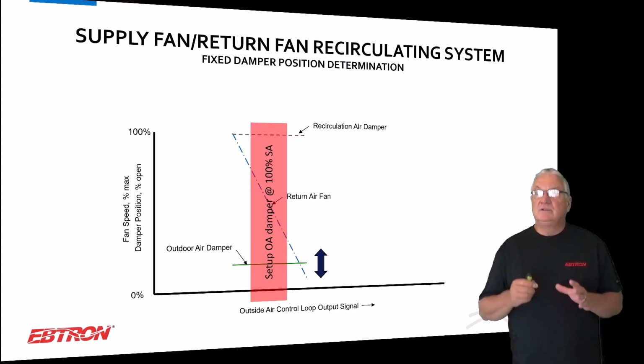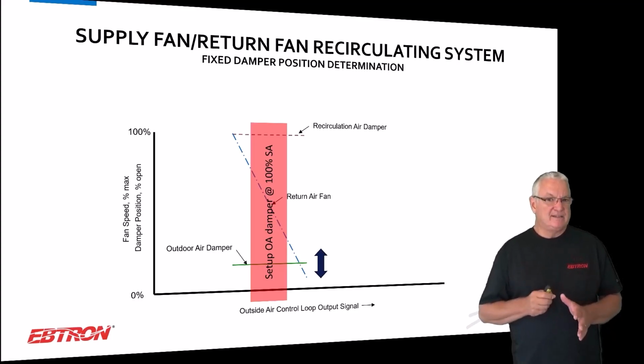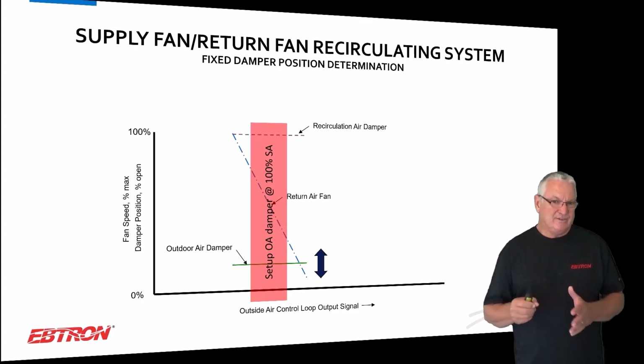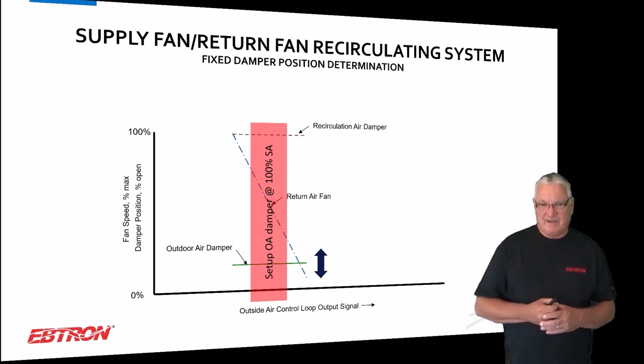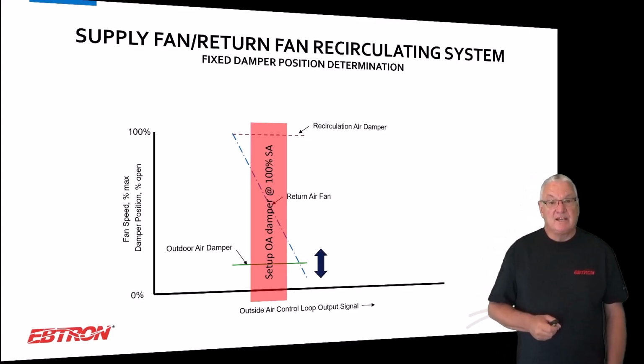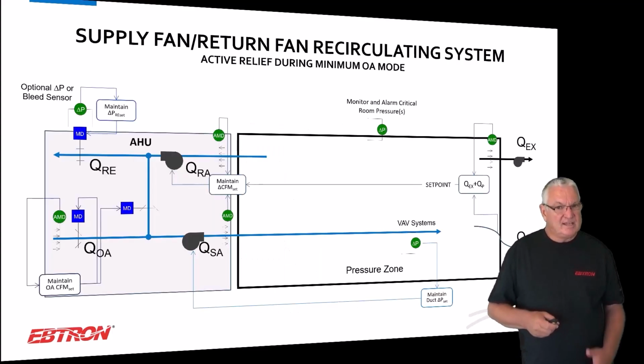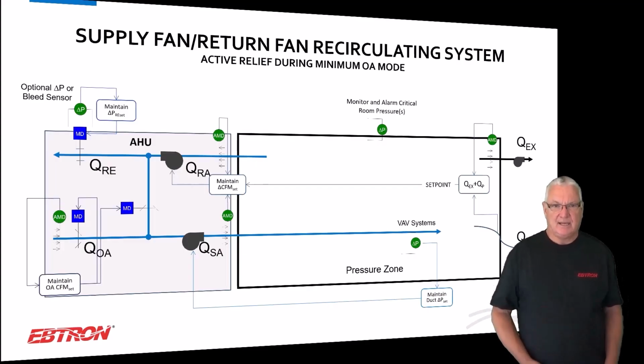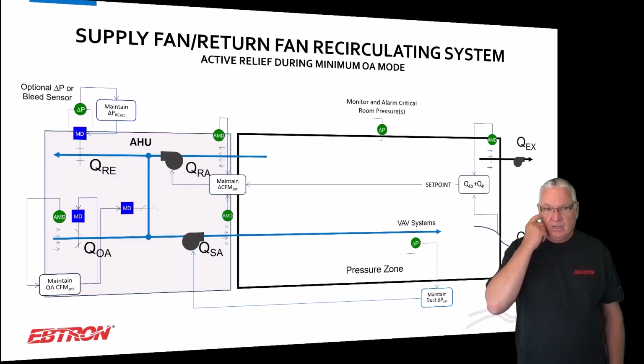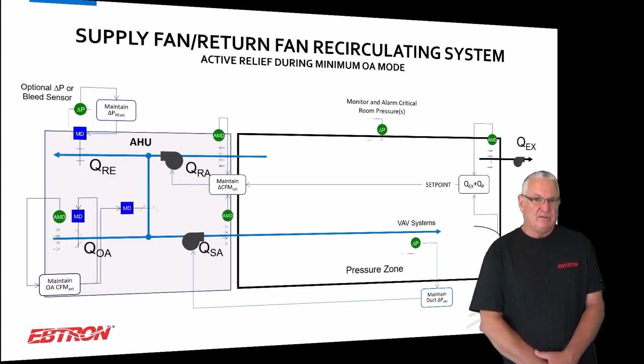Okay, so you want to make sure that everybody's happy with the outside airflow measurement before you do this, or else you're kind of wasting your time. So get everybody in there, say, yes, I'm happy with the flow meter, and then use the flow meter to set the system up. Like I said, that's the trickiest, and you may not even have applications like that. All right, now supply fan with the return fan. When you have active relief during minimum outside air, and I know we're talking healthcare.